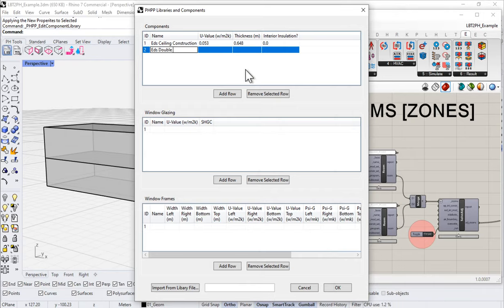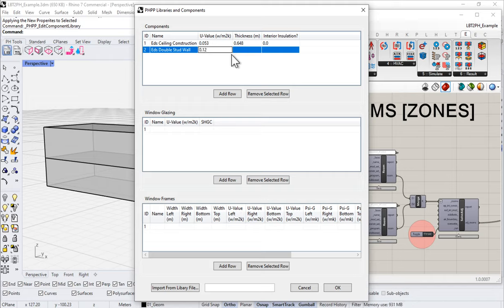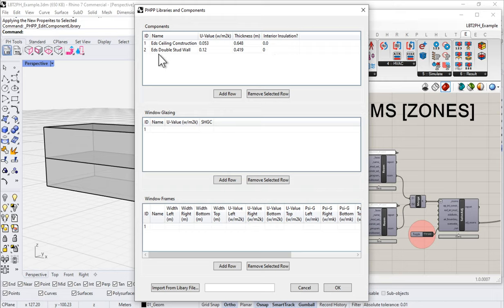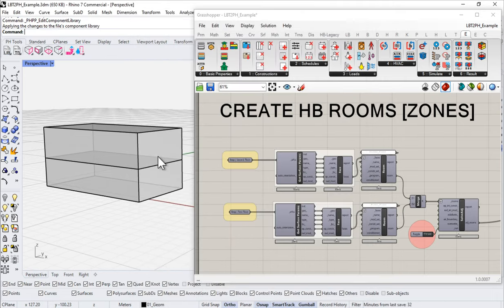I can take this information and enter it into my library. Let's call this 'Ed's double stud wall.' We said we had a U-value of 0.12, a thickness of 0.419, and it was not interior insulated — that has to do with retrofits to existing masonry walls. So we put a 0; if it was, we would put a 1.